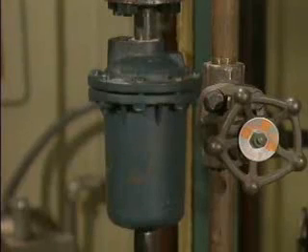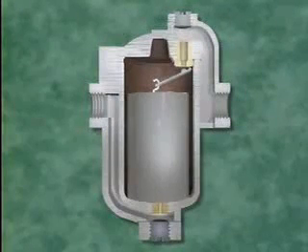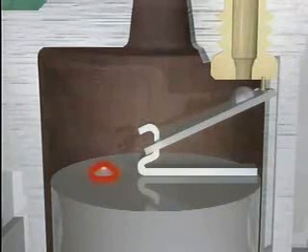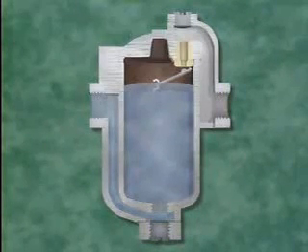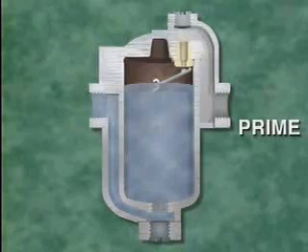Mechanical steam traps operate in response to the difference in density between steam and condensate. One common type is an inverted bucket, or IB, trap, named for the open float contained in the trap's cylindrical casing—a bucket-shaped device that's been inverted or turned upside down. The top of the inverted bucket has a small hole or vent that allows air and non-condensable gases to leave the bucket and collect in the cap area of the casing. The top of the bucket also has a clip attached to a connecting rod, which connects the bucket to the trap valve.